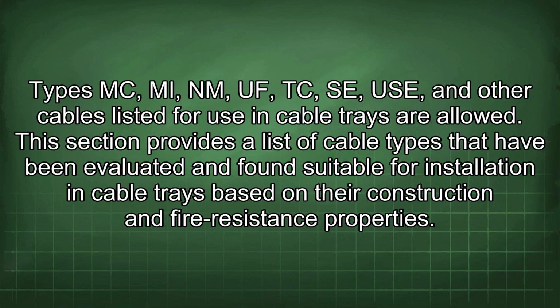Section 300.23 specifies the types of cables permitted in cable trays. Types MC, MI, NM, UF, TC, SE, USE, and other cables listed for use in cable trays are allowed. This section provides a list of cable types that have been evaluated and found suitable for installation in cable trays based on their construction and fire resistance properties.